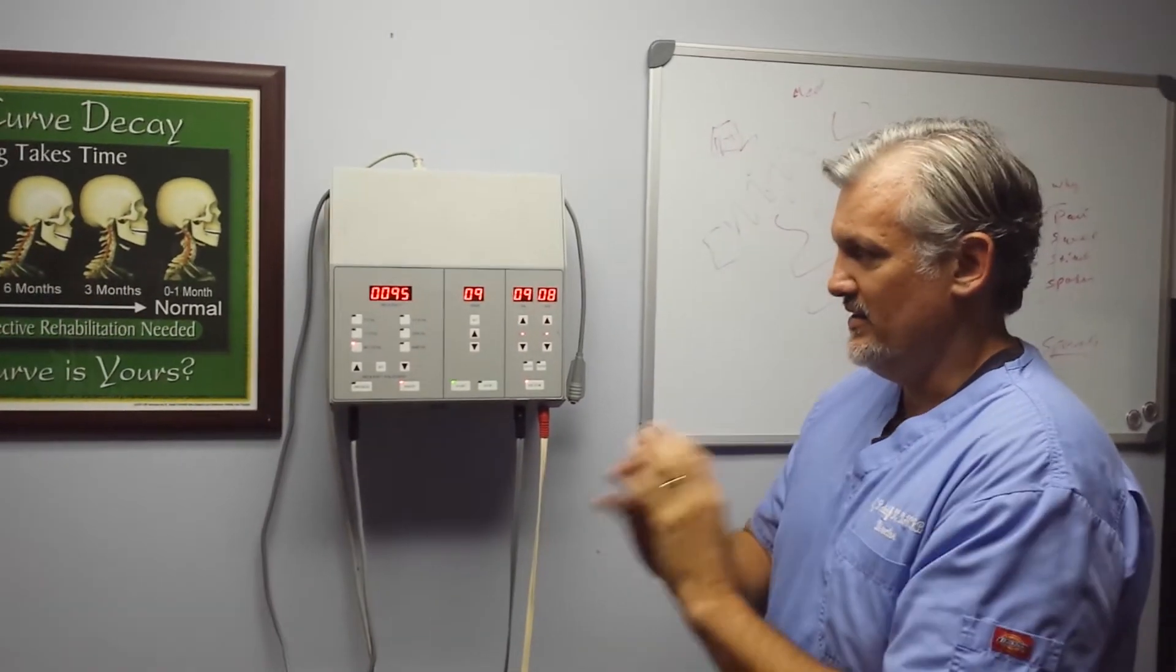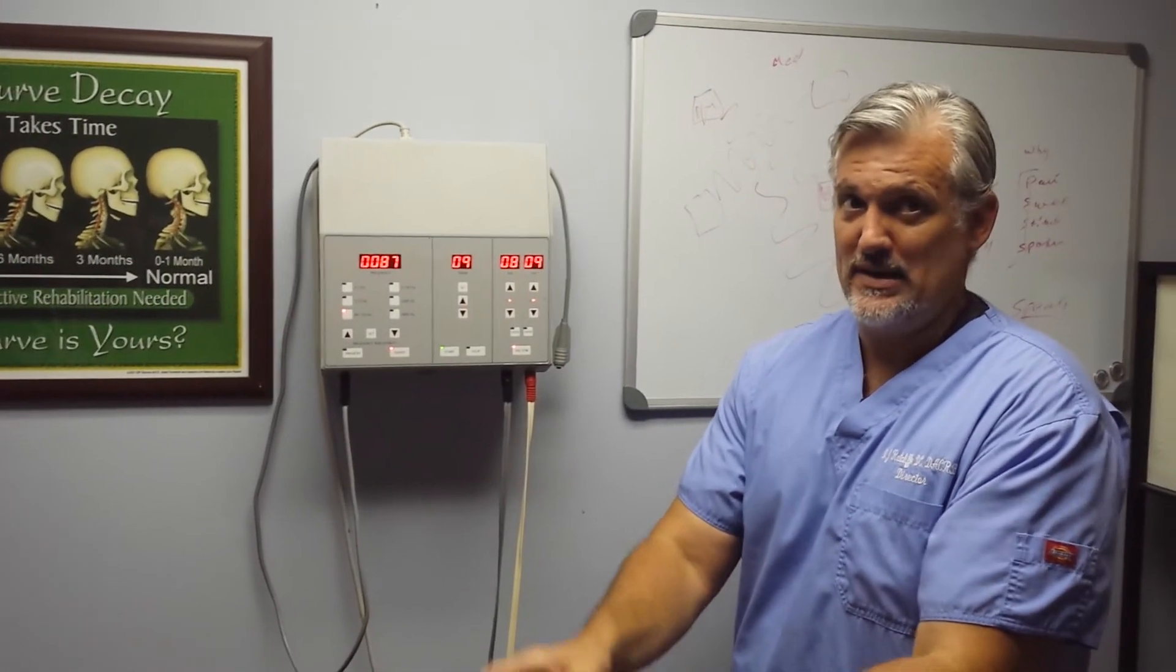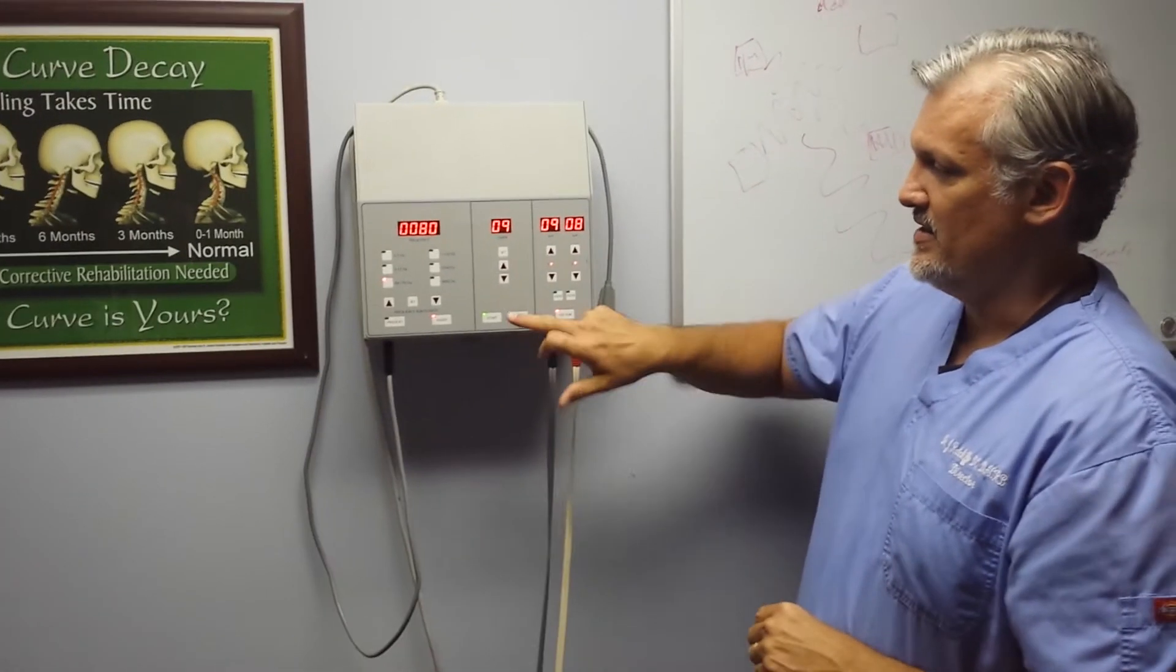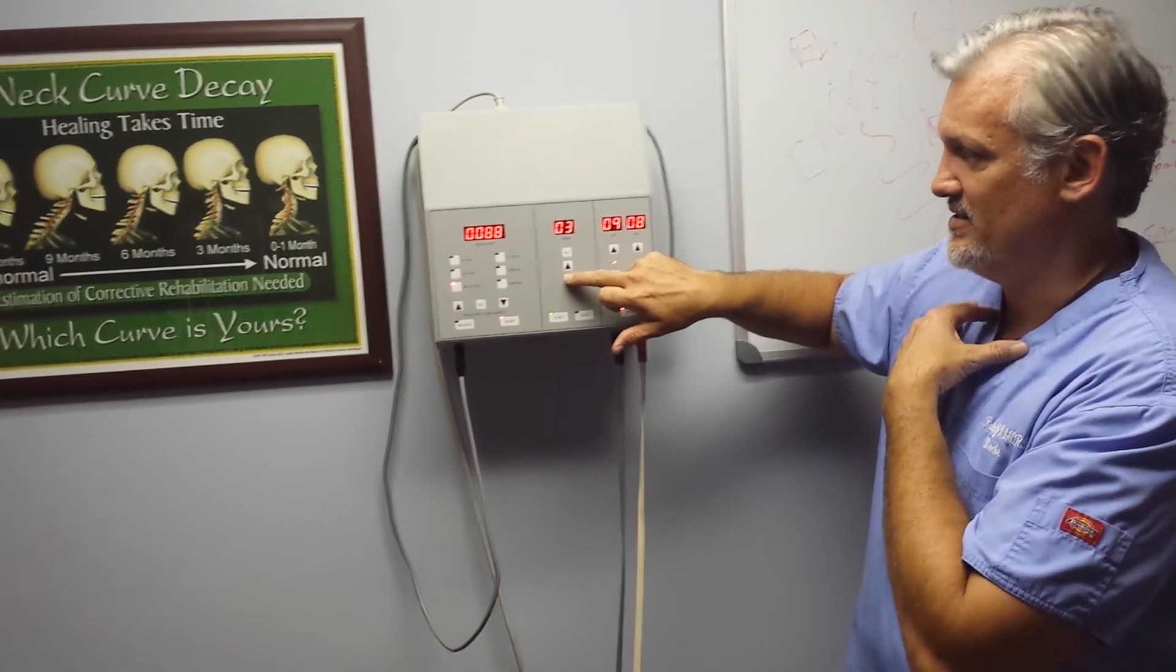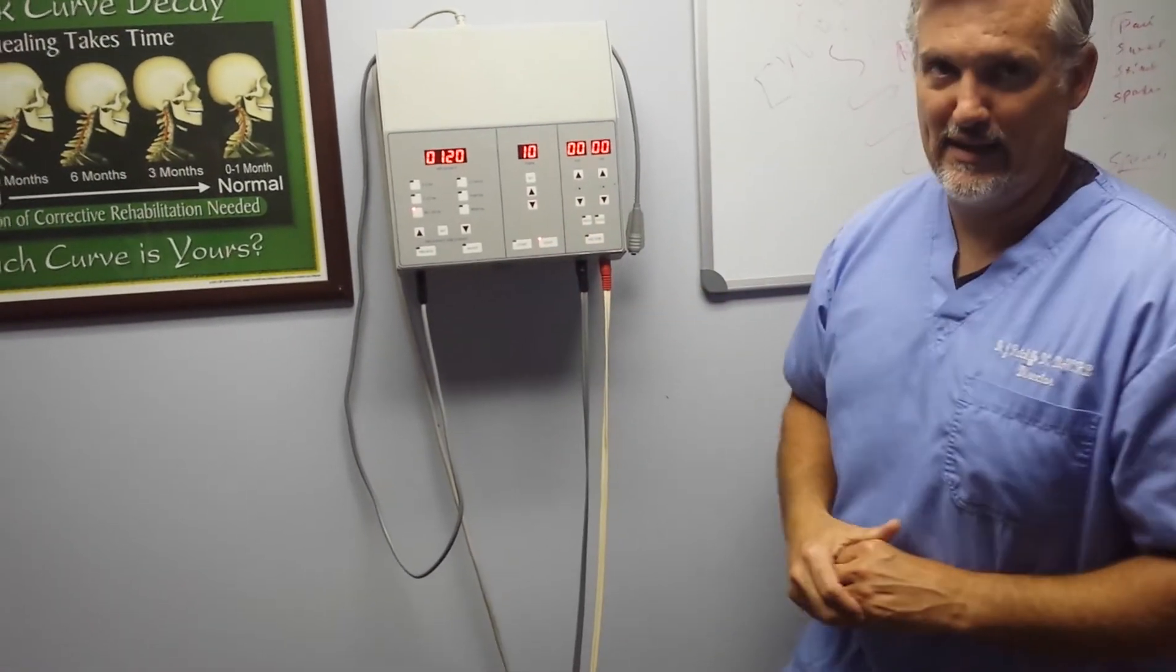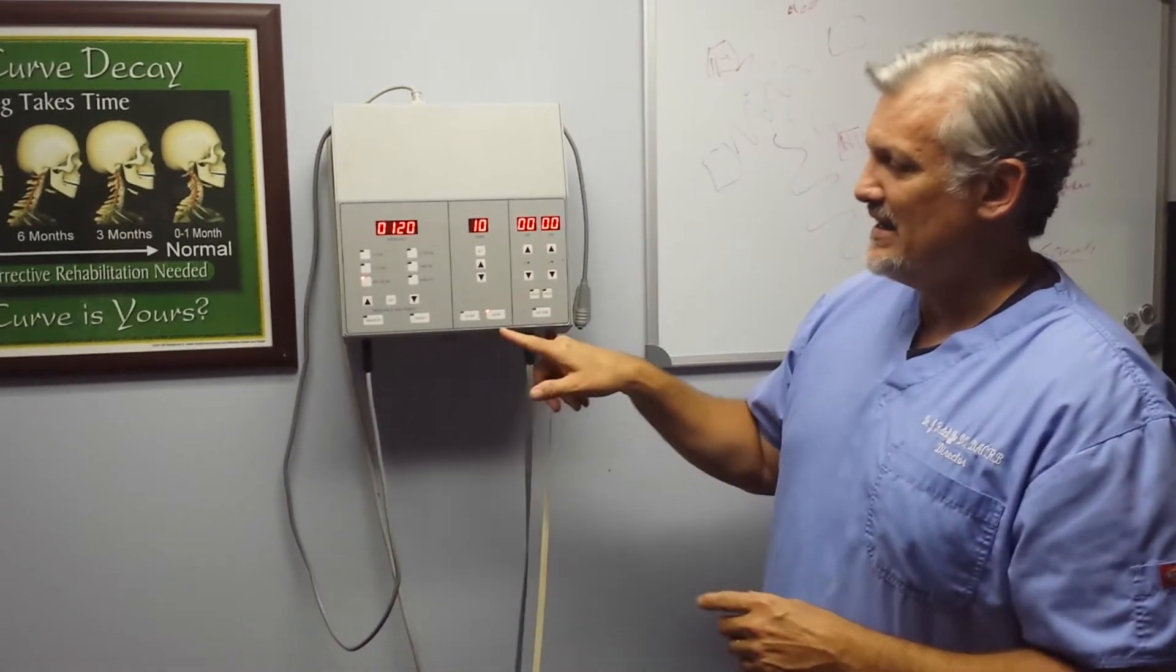Now when you approach the machine or approach the patient, you don't want to just rip the pads off. You're going to shock the patient and sometimes shock yourself. You always make sure that you hit the stop button. I always just as a habit push the stop button again whenever I approach the machine. Even if I know it's off, I just make sure it's off. It also resets the timer to 10 minutes for the next person.